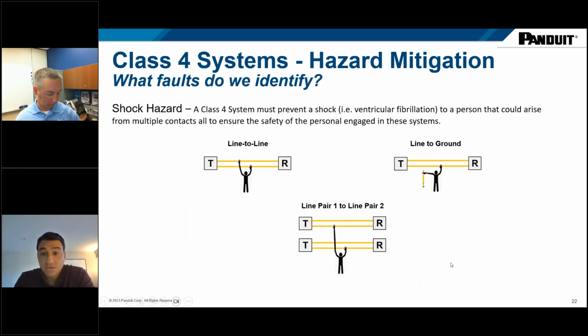When we look at shock hazard faults, there are really 3. If you again picture the transmitter and the receiver, now we're talking about a person having 2 touch points. It doesn't necessarily have to be the hands. And you basically have 2 copper conductors, so line to line, they're touching each of the lines, line to ground, and then you can also have a line to line from the other pair. So you picture multiple copper conductors sending this class 4 power, and a person touches one conductor from one line and the other conductor from the other line. All these faults, the system must be able to detect and turn off.